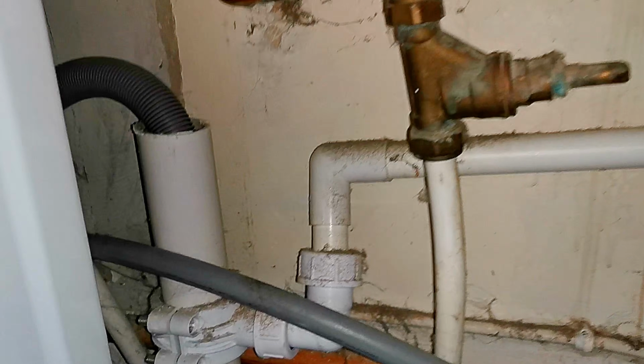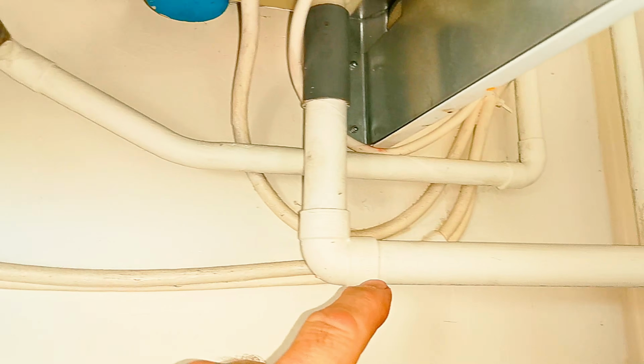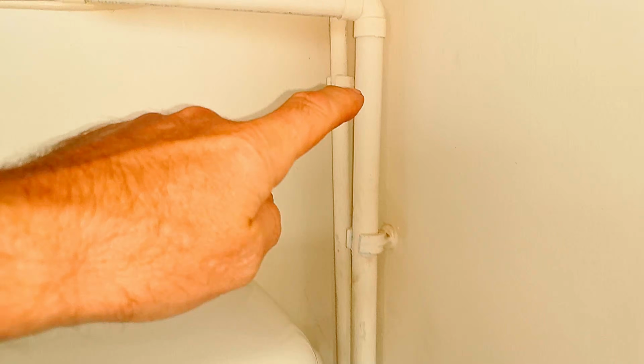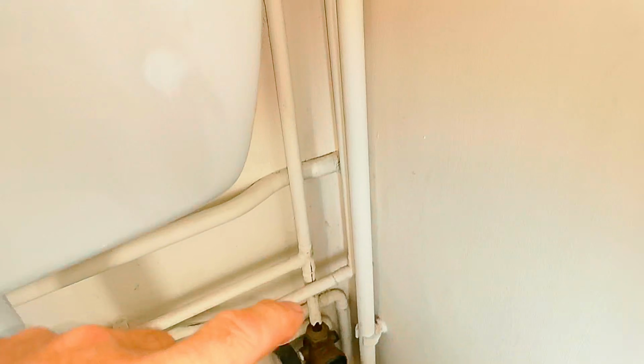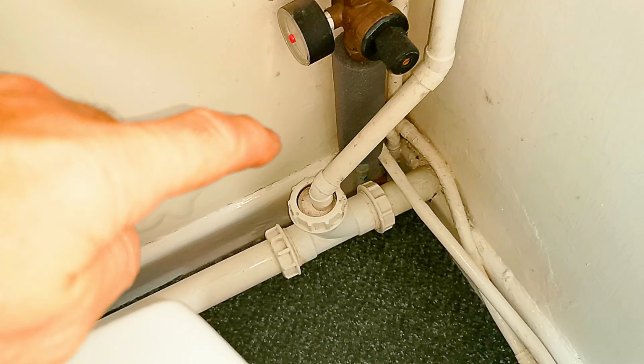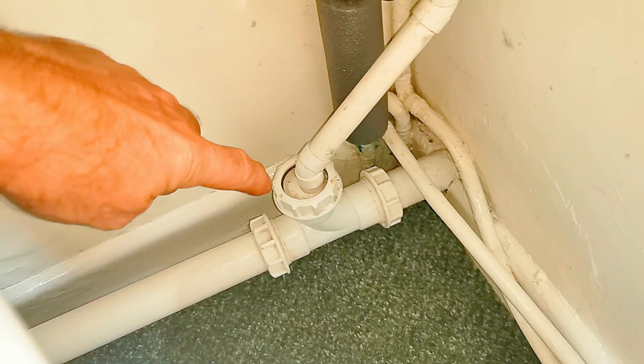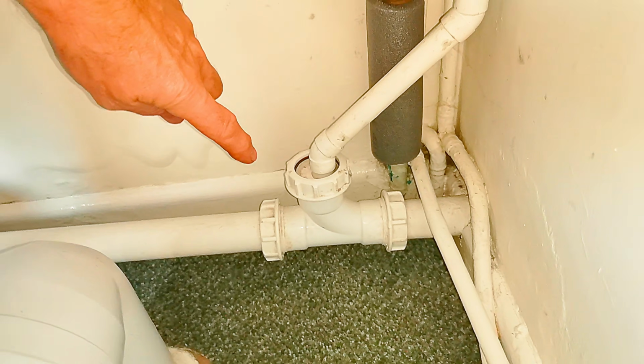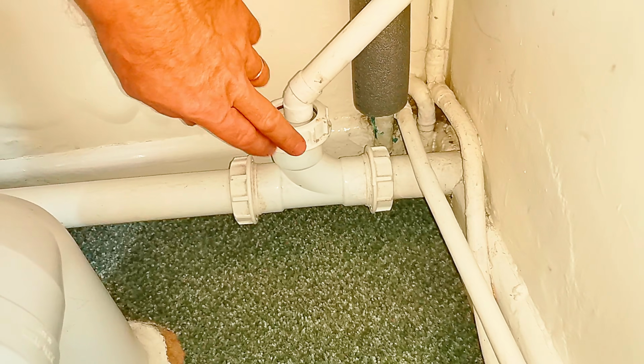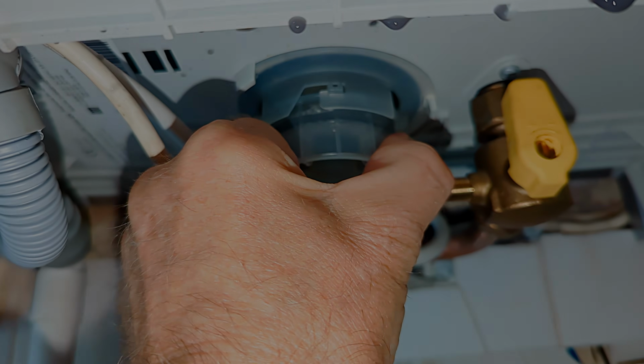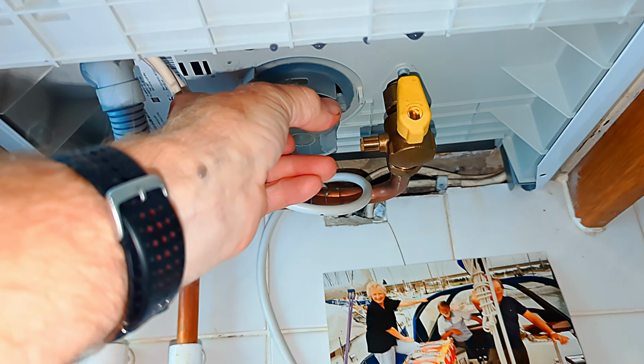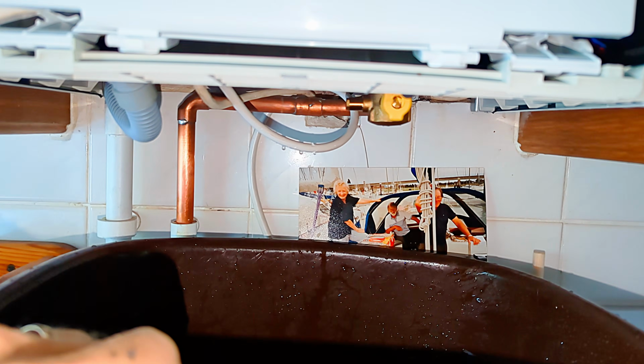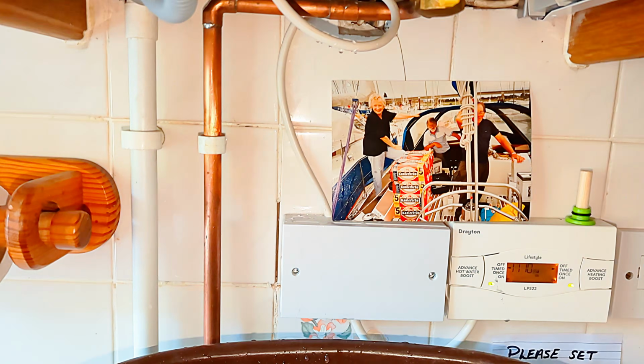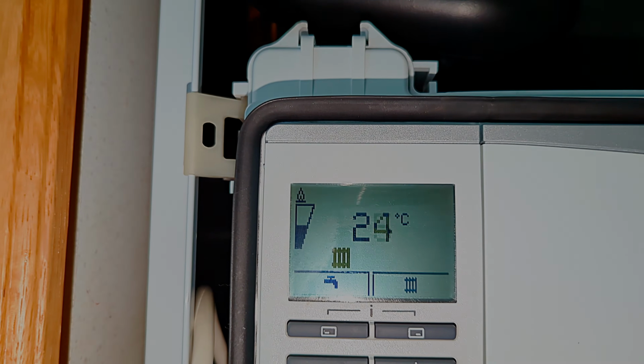So you should see a white plastic pipe connected onto the bottom of your boiler, which would be ideally connected onto your wastewater system in your house. So when your boiler is operating, it could be producing a couple of pints of water every hour. And like I said, that water needs to go somewhere. And if it can't run away due to a blockage, the main heat exchanger is going to gradually fill up with water until it stops the boiler from working, which is exactly what has happened here.